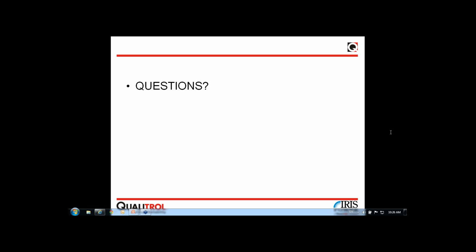Well, we were very careful in the naming of the output from our instrument, and we didn't want to use even the word alarm, because we don't want people to be alarmed with something which is as benign as PD could be. So you have a couple of options there. We definitely do not recommend tripping the machine based on a high level of PD, given the lifetime of the machine and given the levels that could be measured there and still continue safe operation.